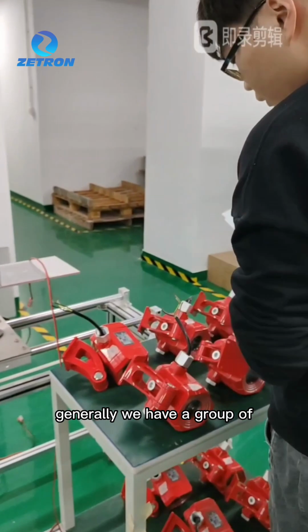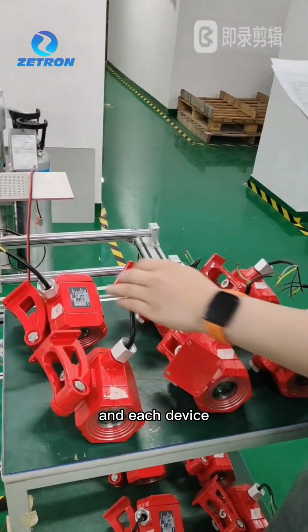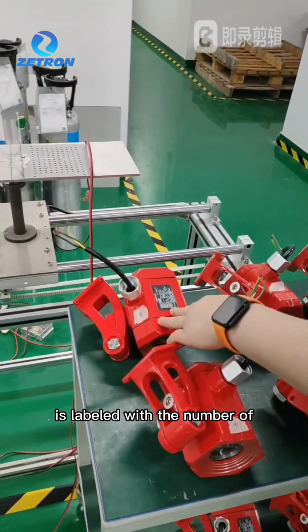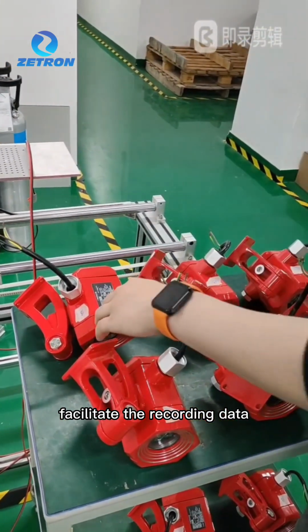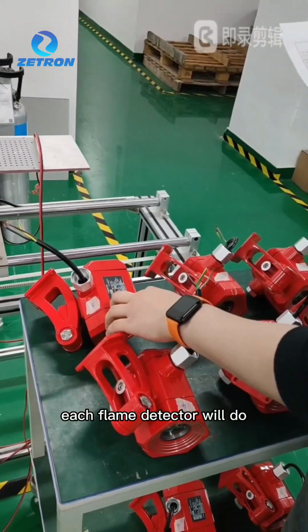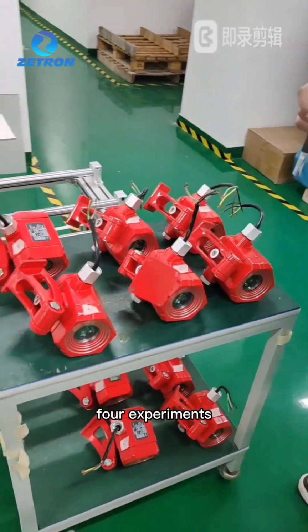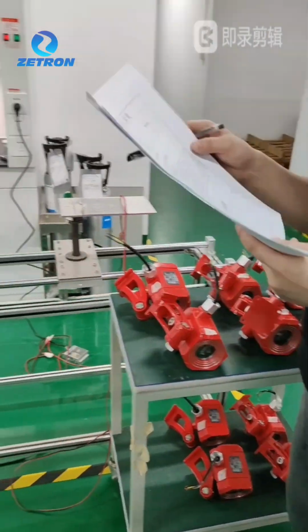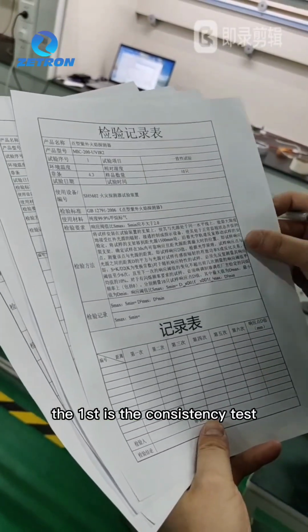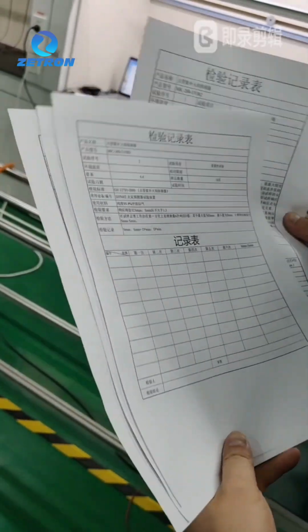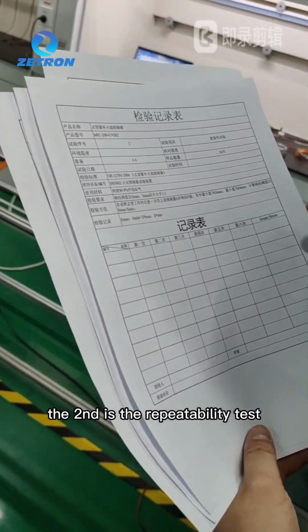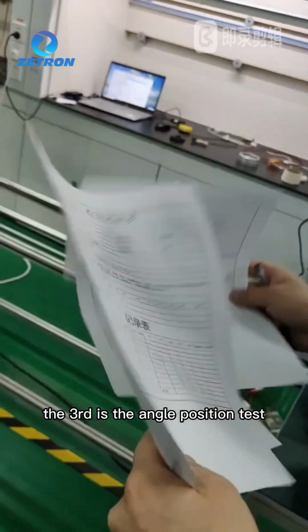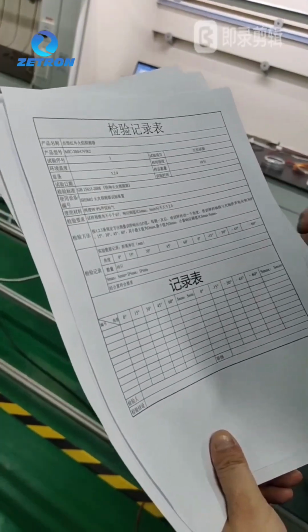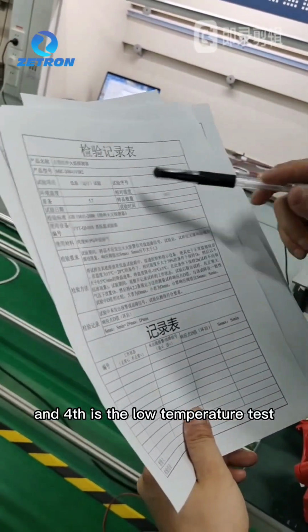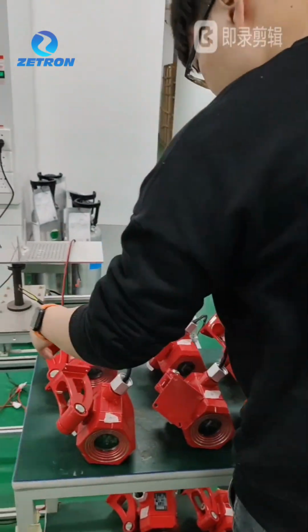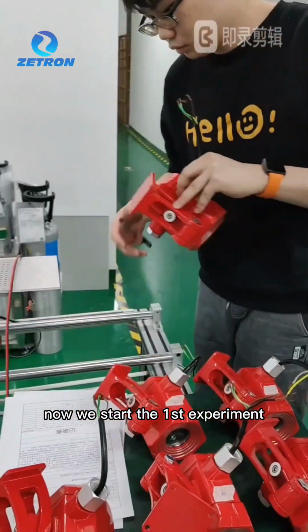Generally, we have a group of 10 flame detectors, and each device is labeled with a number to facilitate recording data. Each flame detector will do 4 experiments. The first is the consistency test. The second is the repeatability test. The third is the angle position test. And the fourth is the low temperature test. Now we start the first experiment.